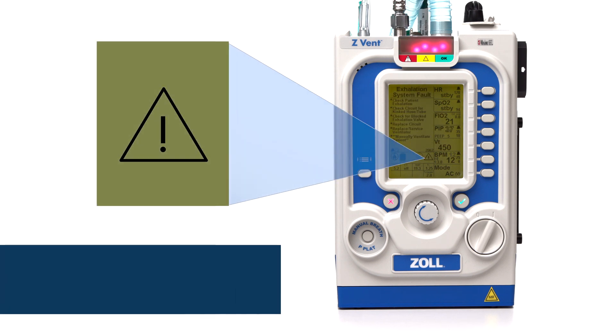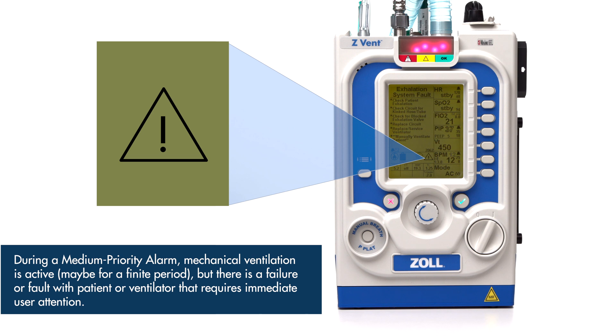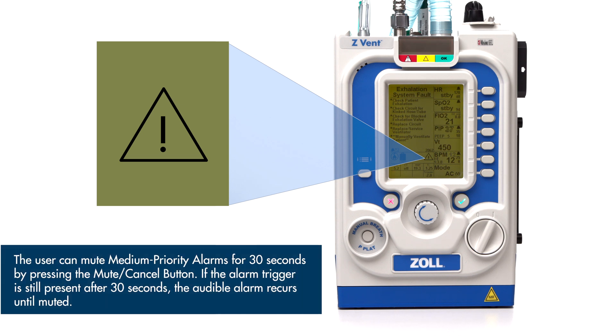During a medium priority alarm, mechanical ventilation is active, maybe for a finite period, but there is a failure or fault with the patient or ventilator that requires immediate user attention. The LED array will either illuminate solid red or slowly flash, accompanied by a slow audible tone. The user can mute medium priority alarms for 30 seconds by pressing the Mute-Cancel button.